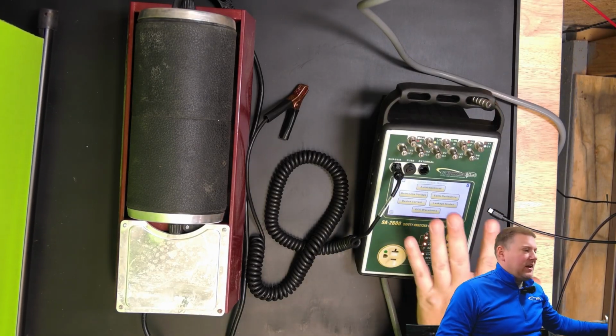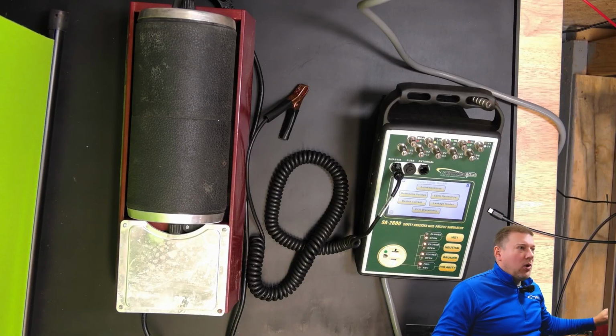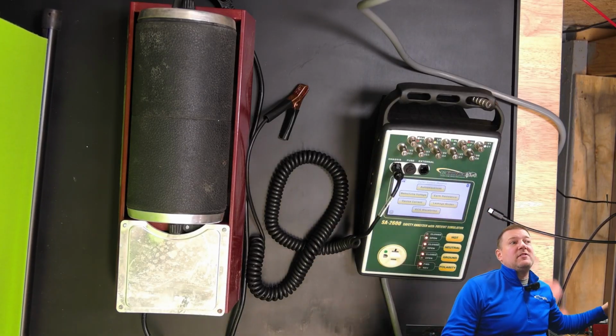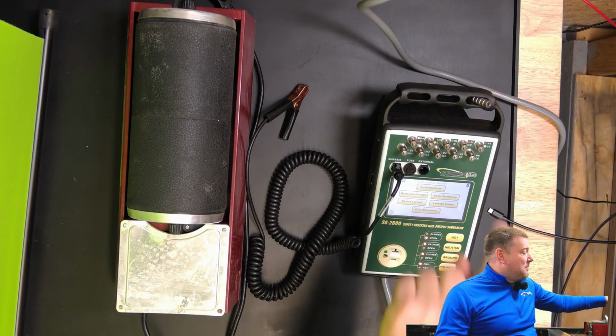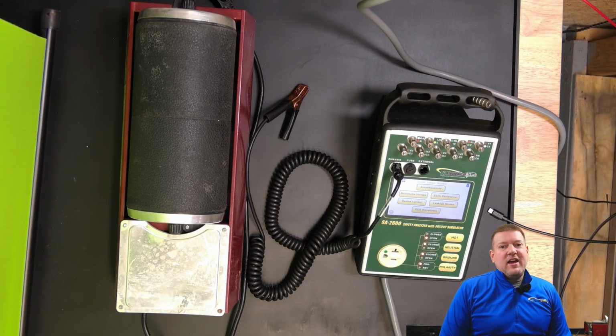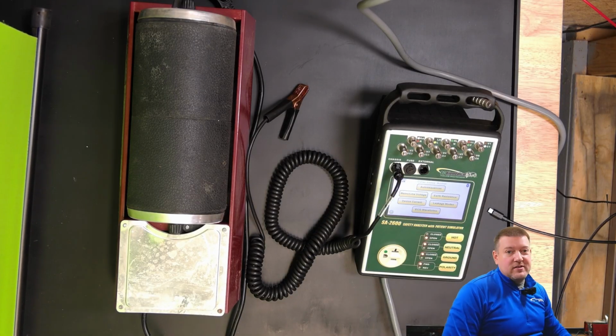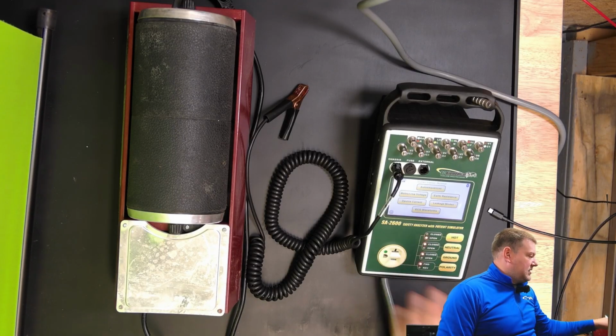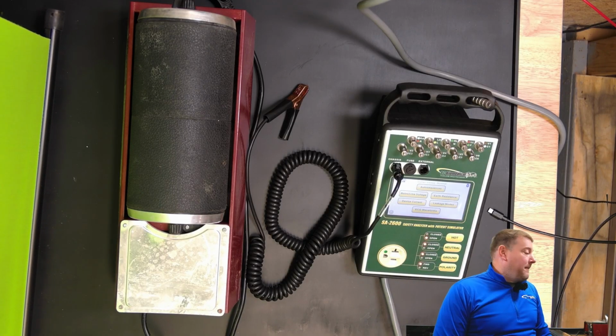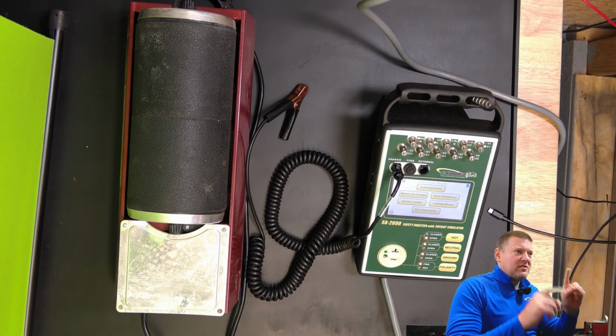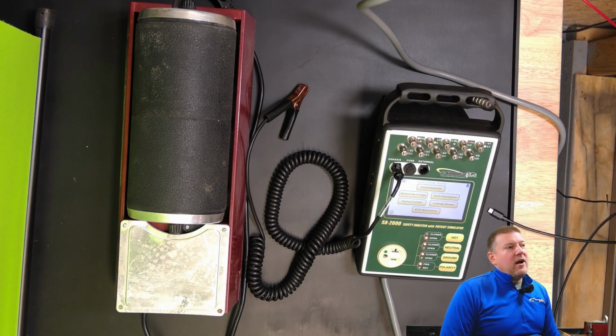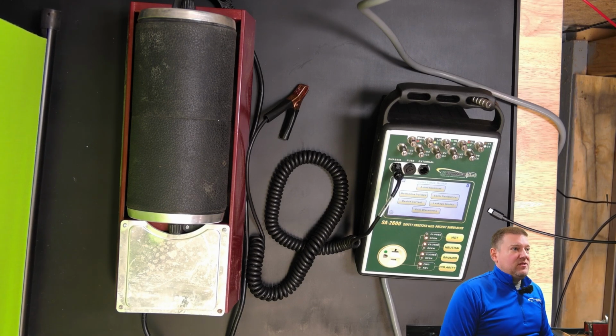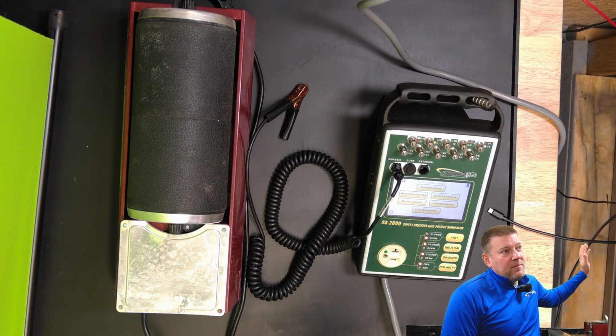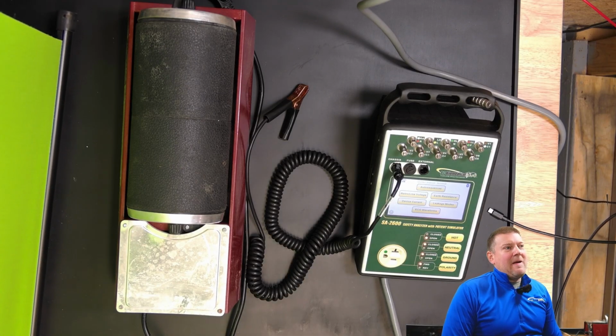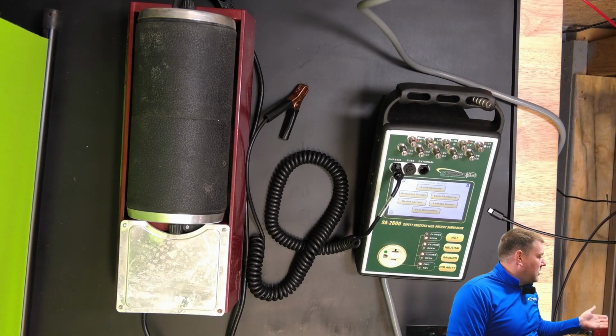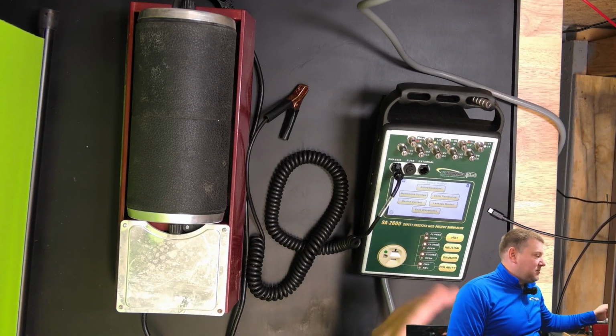And when you plug it in, it's going to give you any error codes, or it's going to analyze your electrical system and see if there's any problems. Now, on my electrical bar back here, I actually had a problem with the ground, and it told me, hey, is this an isolated electrical system, because it couldn't detect a ground. That's probably because it's measuring against neutral and ground to see if it's potential of zero. Come to find out, my power strip is plugged in very poorly in the back, and that was my ground problem. So I've got that remedied, and it powers up just fine now.